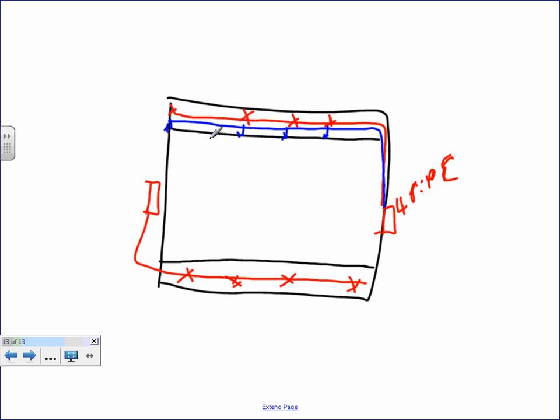One example of that is Minnesota State Statute 299F, residential CO smoke detectors. It says that in any residential occupancy now, you have to have CO smoke detectors in each room within 15 feet of, and in each pathway as an egress out of that room. There are exemptions where, say, if they don't have any CO producing elements in the rooms, but they have a boiler room and a locker room, then as long as they are monitored off-site, you can just put one in those areas. And each fire marshal interprets every code differently, so it's all about learning how they do it.